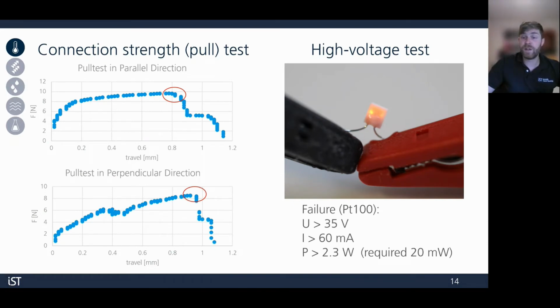So here we have a terminal connection strength test on the left. We test the pulling force needed for plastic deformation, or basically for the wires to come off. So we pull both leads together on the short wire RTD, and we see failure at around 10 newtons when pulling in the parallel direction and around 8.5 newtons when pulling perpendicularly. The general specification deems 2 newtons acceptable.